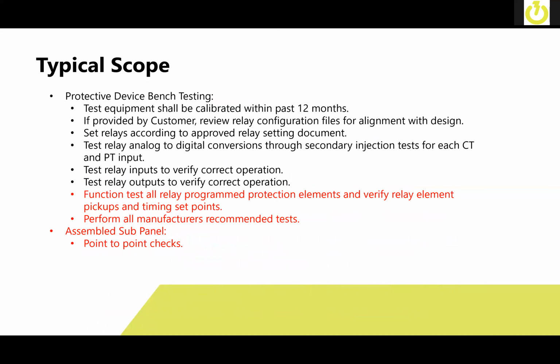From a protective device bench testing, we recommend that test equipment be calibrated within the past 12 months. For instance, you hear Omicron, you hear Doble, you can hear Megger. Those are some common manufacturers of relay test equipment. It's recommended that you get those calibrated. They do drift over time.